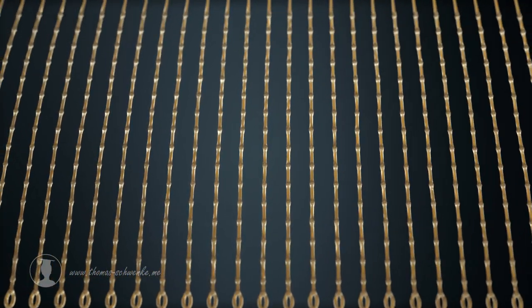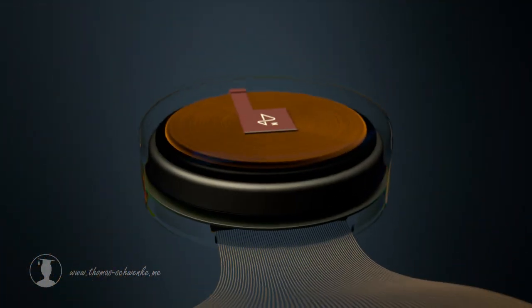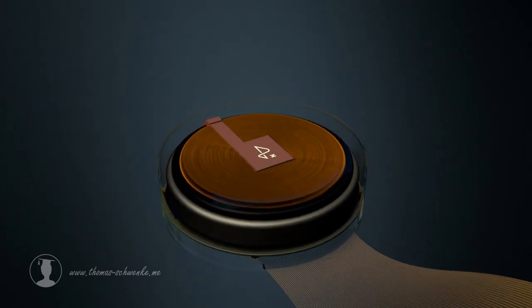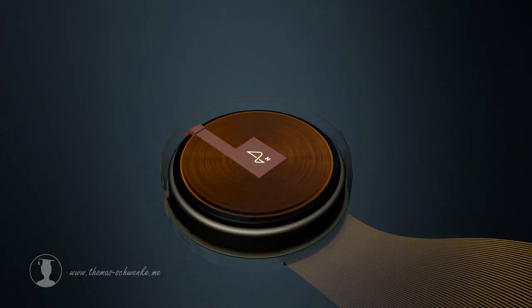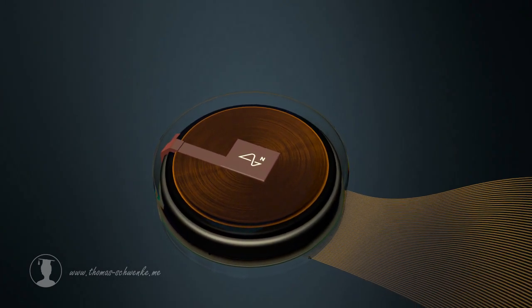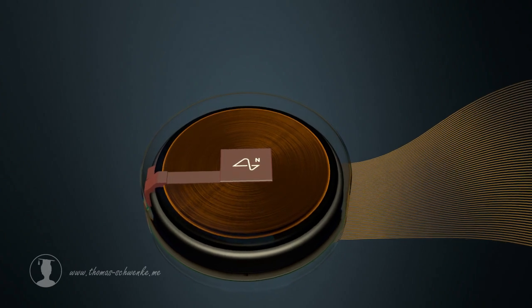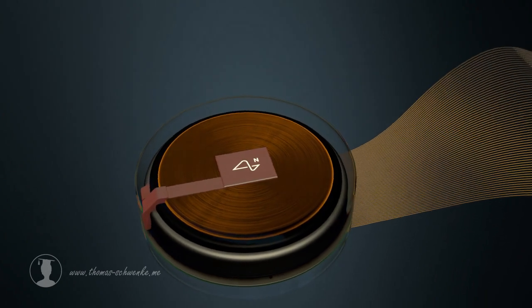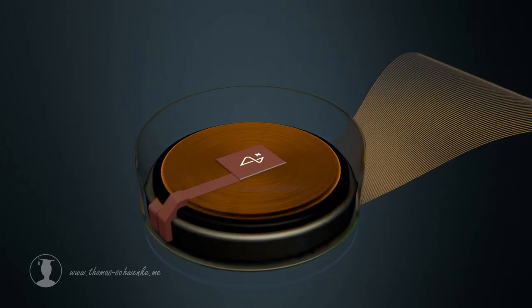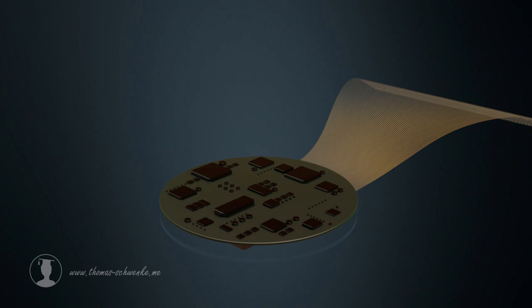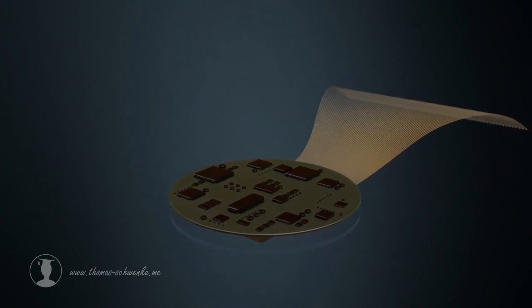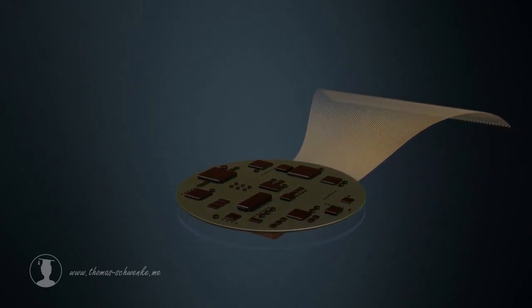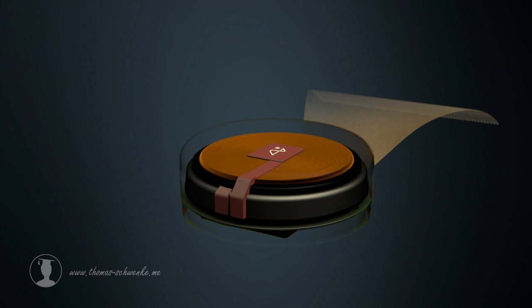Each electrode is connected via its thread to the processing unit of the N1. The housing is made of a biocompatible and transparent material. Underneath is a battery that can be charged wirelessly at night. The computing unit processes the information received from the electrodes and transmits it wirelessly to a smartphone or other devices.